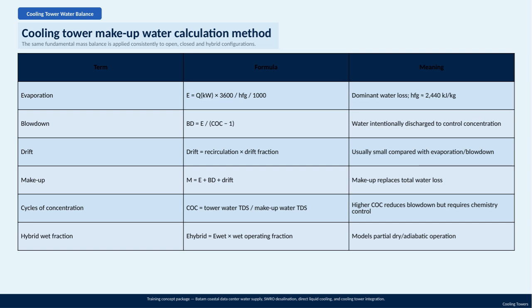Next is blowdown, which is water intentionally discharged to prevent the buildup of impurities. It's determined by dividing the evaporation rate by the cycles of concentration minus 1. Managing blowdown is crucial because it keeps the water chemistry in check by controlling total dissolved solids. Drift refers to small droplets of water carried out with the exhaust air. Although usually minimal compared to evaporation and blowdown, it still needs to be considered in the overall water balance. Makeup water is the total amount needed to replace all losses, evaporation, blowdown, and drift, to maintain the system's water level.